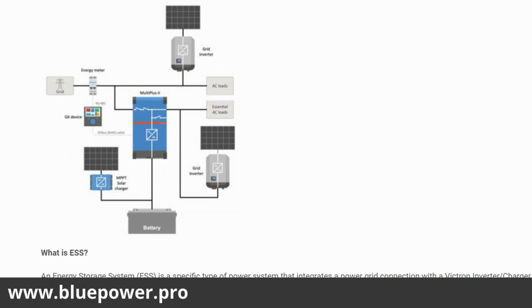So in these types of systems we've got advantages with DC coupled and AC coupled systems. AC coupled is going to have an advantage for households with higher loads during the day. What that does is it will convert PV power directly onto your AC output line, and you've only got the efficiency loss of the grid tie inverter feeding your AC loads. Same goes for the DC MPPT. For charging your battery, it's going to be just the efficiency loss of the MPPT of the power going to your battery. Yes. Silly question.